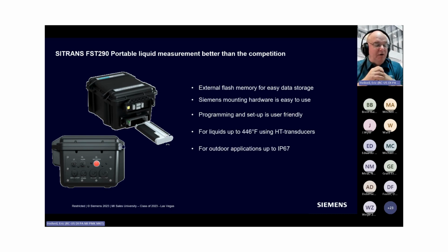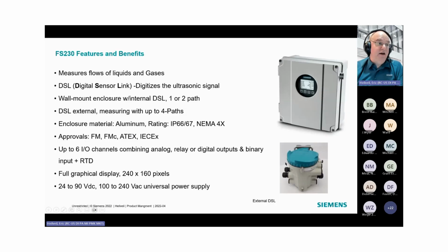So it's a check meter, it's a flow meter. You can use it as a permanent install, but it's really designed to be moved around. It stores up to 20 locations within its memory. So you can actually take this and program it, and then when you want to go back to that site, you just recall the site, and installation takes 5 minutes instead of 40 minutes or less. As I stated earlier, you can use high temperature transducers, good to 446 degrees, and again, IP67 installation.